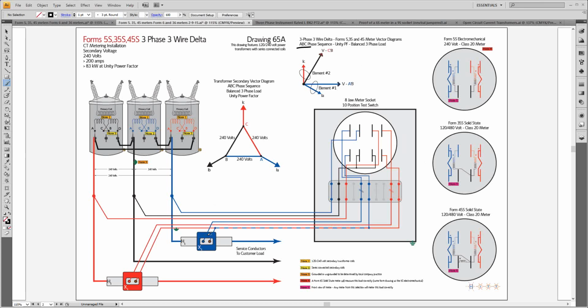Again, with the idea that I'm metering the current in the blue phase, which I'm calling A phase. I'm metering, or putting a CT in, the red phase, or what would be C phase. And this conductor, the current that flows in this conductor, goes unmetered. There's not a CT here to measure it. And so Blondel says if I have 3 wires, I need 2 meter elements. Each one of these meters is a 2-element meter.